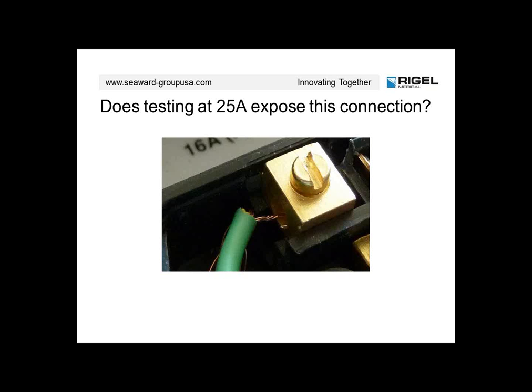Here's a little diagram of a test that we have done where we've taken the cable and cut away a number of the strands of the wire. At 25 amps, this would pass the ground bond resistance test. The only way this would show up at 25 amps is if the current was left on for a long period of time, and then of course you start to have heat build up on those small conductors that are still left, and they would get very hot and start to burn away. 200 milliamps would define this as a poor connection and give us some exposure as to the ground wire not being intact or not being as well connected as it should be.